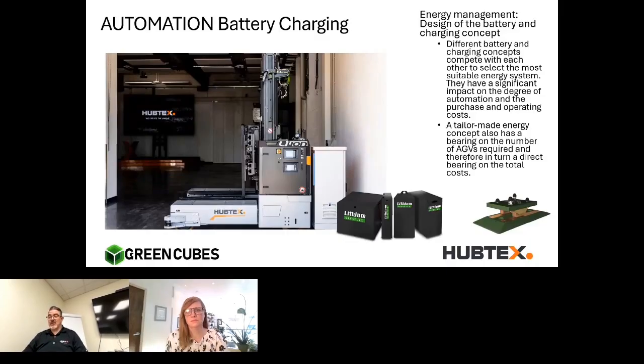You can charge for 15 seconds, 30 minutes, or an hour without any degradation to the battery. The AGV can constantly be running, because if you're doing an AGV, you're not a single shift application, you're running multiple shifts, and the AGV should never stop. So charging is very important, and that's where lithium comes in—it allows you to do high current opportunity charging.